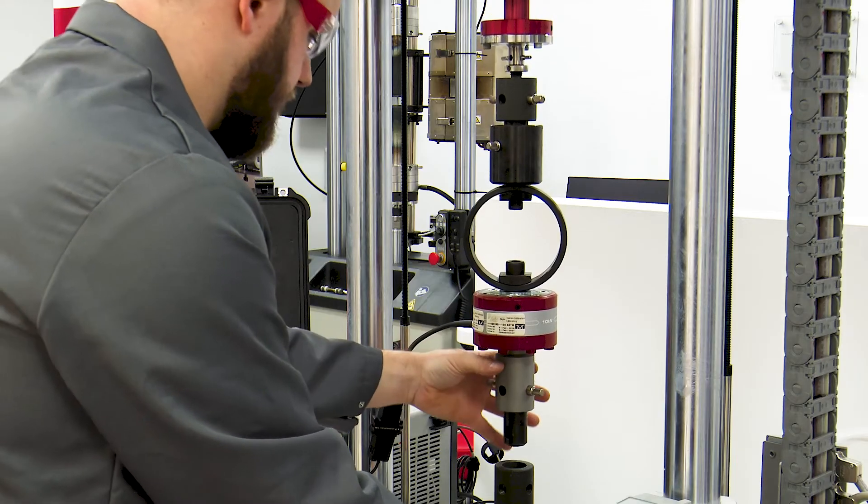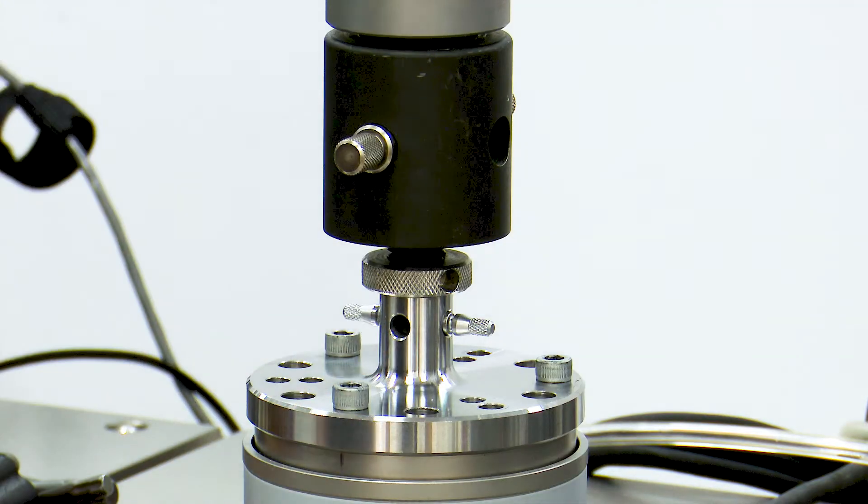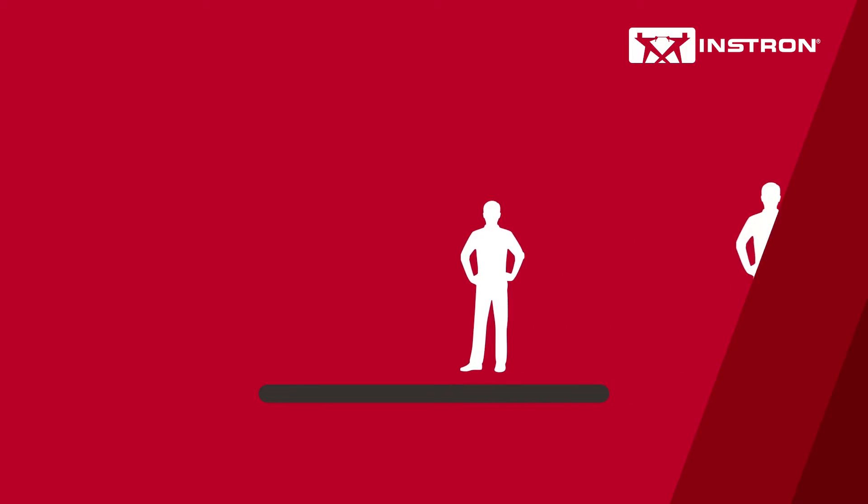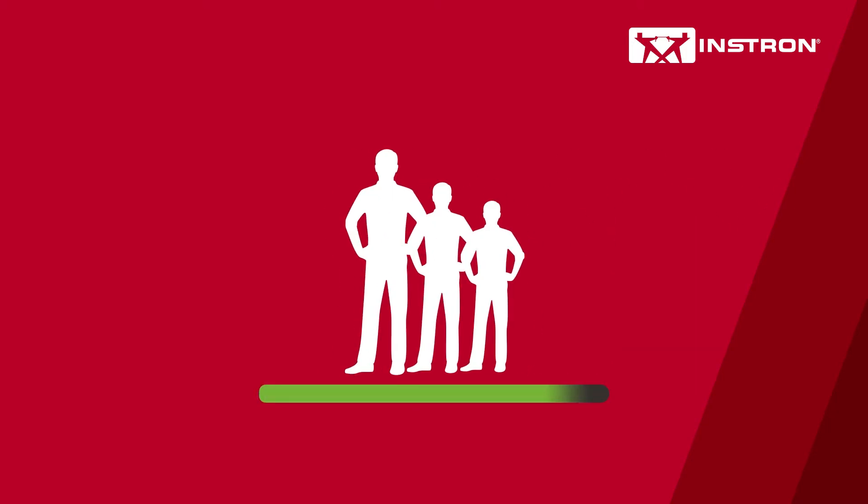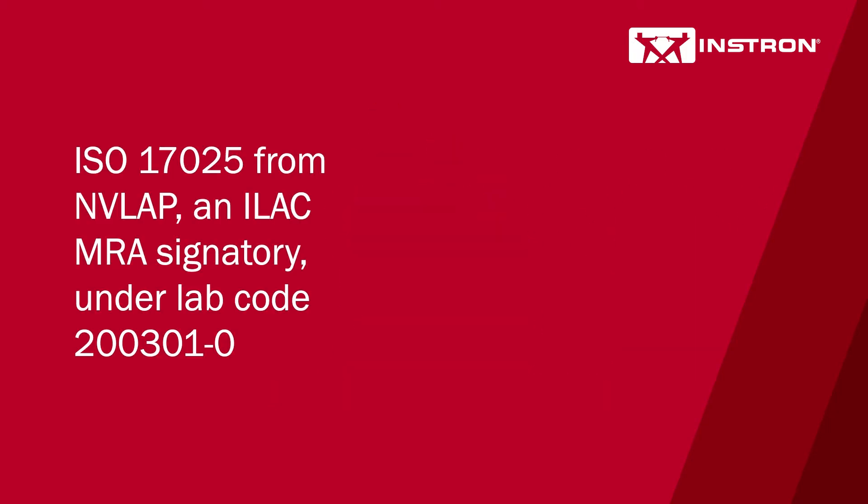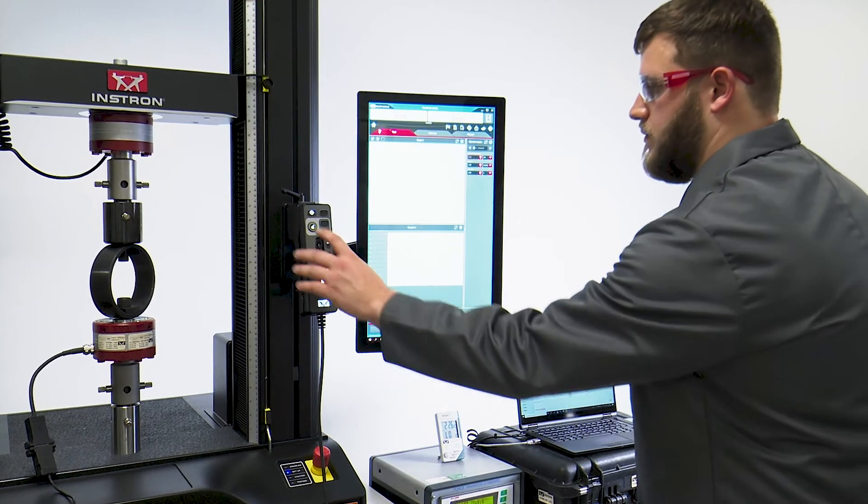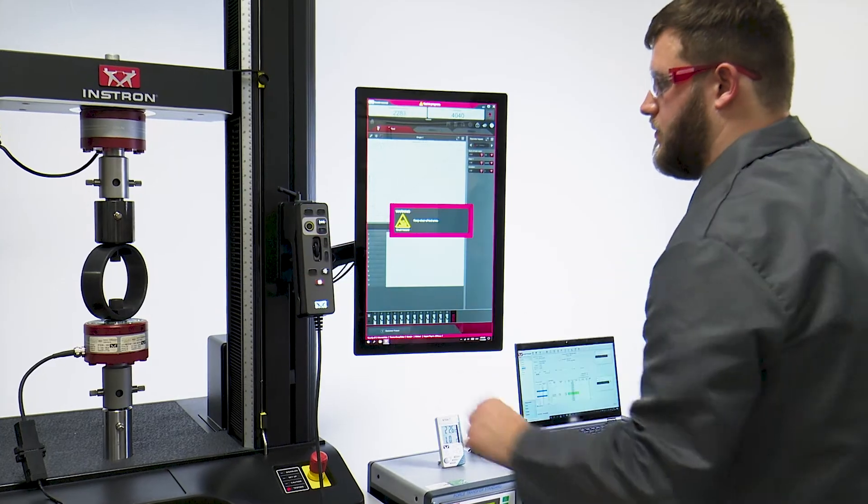Regardless of the force calibration service you require, it's worth noting that all INSTRON field service engineers who can deliver our calibration services are audited in accordance to ISO 17025 from NVLAP and ILAC MRA signatory under lab code 200301-0. Our accredited force calibration ranges cover one gram up to five mega newtons.